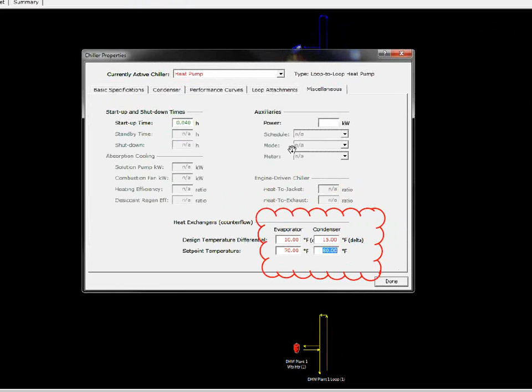So once I had the chiller set up, this is under the miscellaneous tab. These become available, I believe, after I set the chiller to loop. These are my temperatures for my heat exchanger, basically what the geothermal is going to be providing to the loop, and what the cooling tower is going to be providing. In the design, the loop is going to be 70 degrees. I don't think it would run if I set the condenser to 70 degrees as well. I think it would crash out on me.